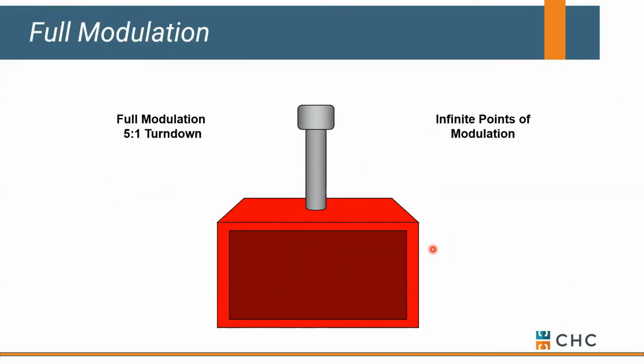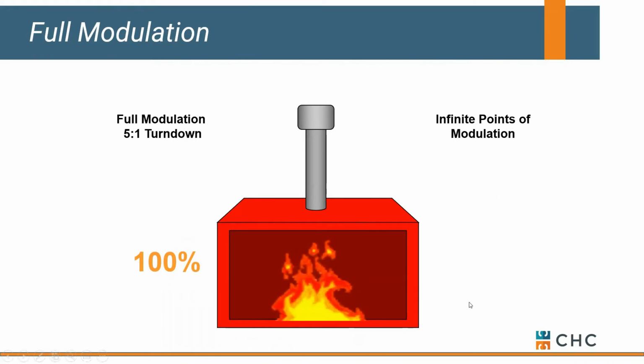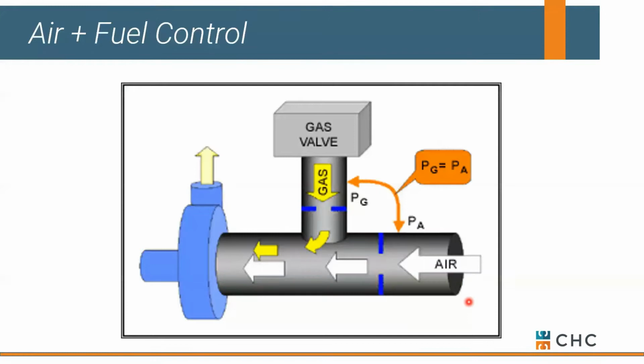More common though, we're talking about modulation, and that allows your boiler or your burner to fire at a minimum firing rate and then increase as needed and operate anywhere in between. So very flexible, has a lot of advantages for tracking load and dealing with flexibility or changes in our system throughout the day. One thing you might ask is, how do we maintain good combustion as we modulate our burner or our blower up and down, okay, as we speed things up or slow them down?